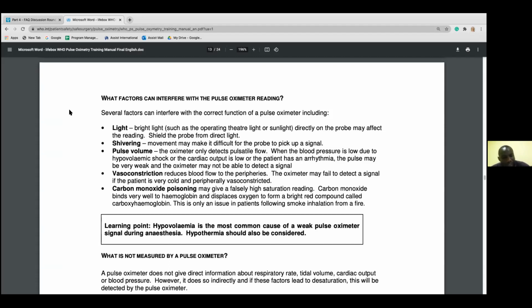There are other factors such as ambient light. You need to make sure that when you place the pulse oximeter probe on the finger, you follow the correct orientation and instructions on the probe so that you avoid the external light, the ambient light, actually interfering with the measurement of that pulsatile nature of blood and the oxygen saturation.